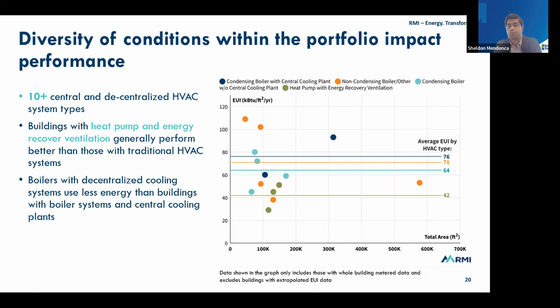On the right-hand side, the graph shows EUI on the y-axis and building size on the x-axis. We can clearly see that buildings with heat pumps and energy recovery ventilation were the highest performing, with an average EUI of about 42 kBTU per square foot per year. What was counterintuitive was that condensing boilers with central cooling plants had a higher EUI than condensing boilers without central cooling plants. This is counterintuitive because central cooling plants are generally more efficient than through-the-wall or window AC units, but we believe this is due to occupancy and tenant end use, and because central plants also serve more of the building, like common areas, throughout the year.